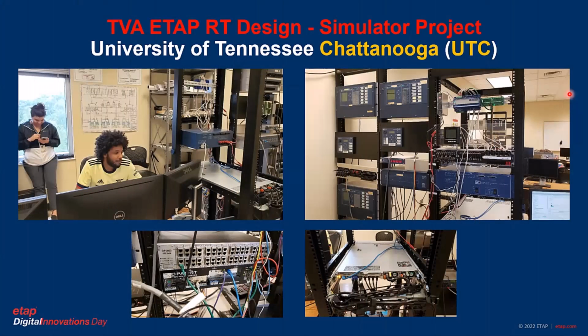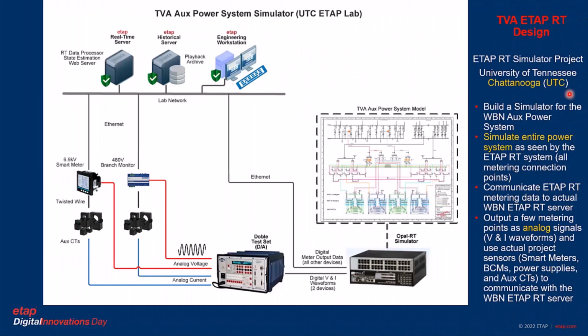One thing I'm very excited about is we've decided to build a simulator of our Watts Bar auxiliary power system at a local university. That's the University of Tennessee at Chattanooga. And I've got some pictures here of the graduate students that are working on this project. But we actually built a simulator. And the idea behind the simulator is that we would simulate the entire power system as seen by the ETAP RT system. In other words, all metering connection points. So they're using an Opal RT simulator with our TVA auxiliary power system model inside it. And then we're going to output the digital output of each of those points back to the actual ETAP real-time server that we're going to be installing at Watts Bar.